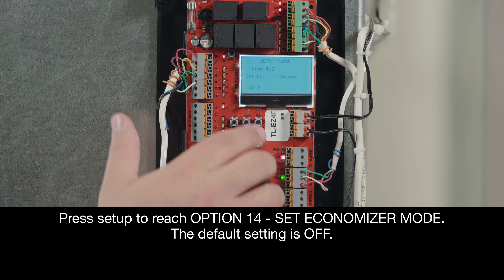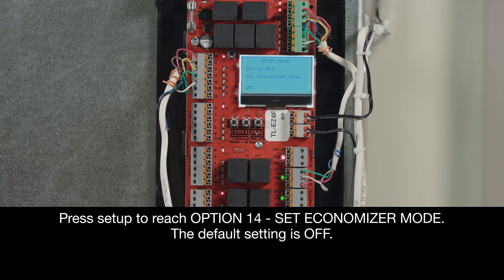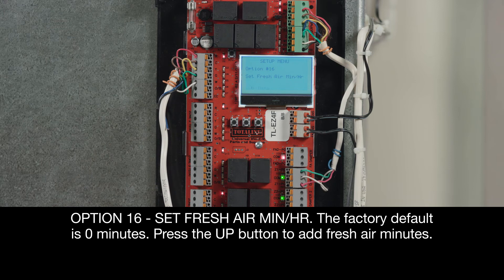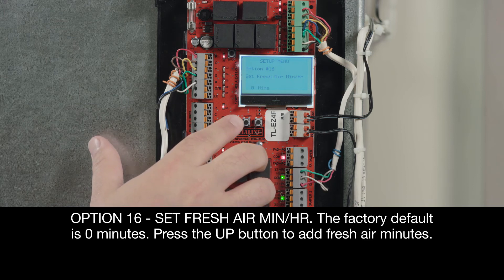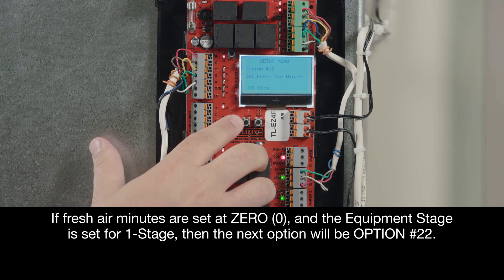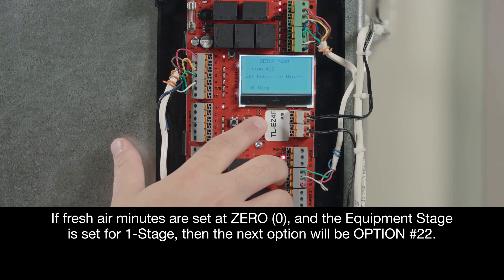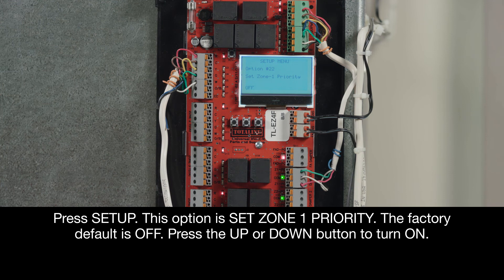Now we'll press Setup to reach Option 14, Set Economizer Mode. The default setting is OFF. And let's go to Option 16, Set Fresh Air Minutes Hours. The factory default is 0 minutes. Press the Up button to add fresh air minutes. If fresh air minutes are set at 0 and the equipment stage is set for 1 stage, then the next option will be Option 22. So press Setup to get there.